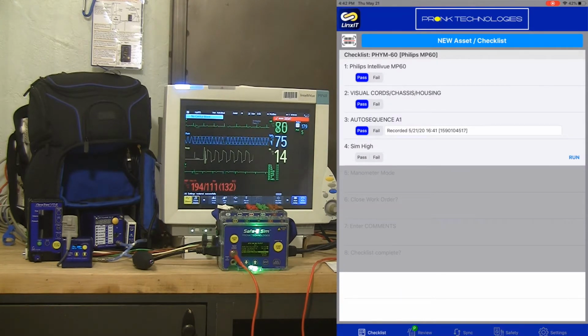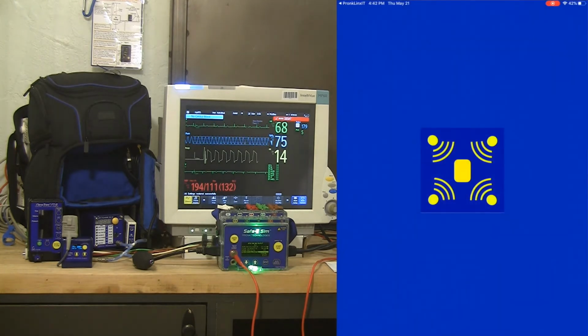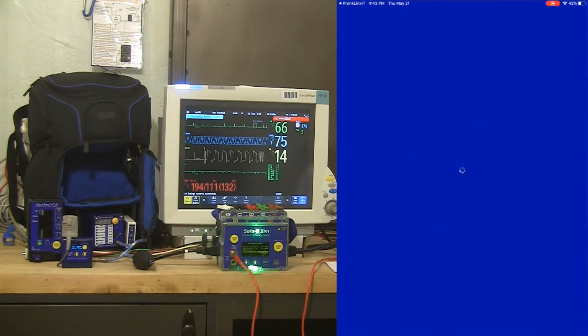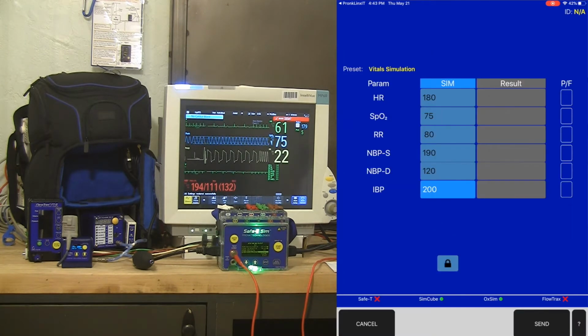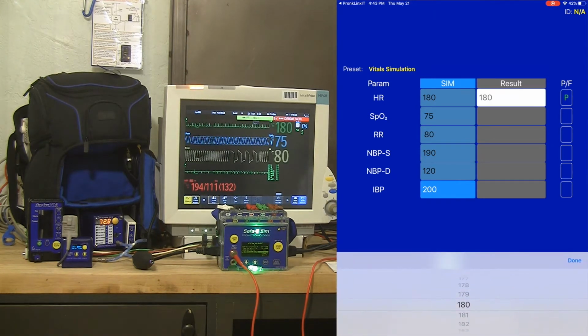From here, I'm going to run a series of simulations that are immediately synchronized when I touch the run button on my iOS device. I've got all of these parameters immediately simulating what I predefined at the instant I get to this screen. I'm going to go ahead and start an NIBP reading on the monitor, but in the meantime, my heart rate simulation should be 180. I can see it's 180.